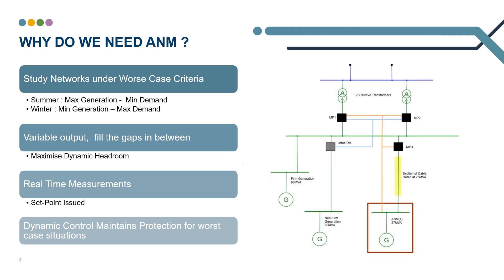This schematic diagram shows a relatively simple example where we have two 90 MVA transformers feeding a wider network. Worst case studies dictate that we can't go over 90 MVA firm capacity, as if we lost one transformer, the other one's going to be overloaded. Another 90 MVA of capacity could be connected under a non-firm arrangement using an intertrip scheme, as this is going to disconnect this 90 MVA in the event of a fault.